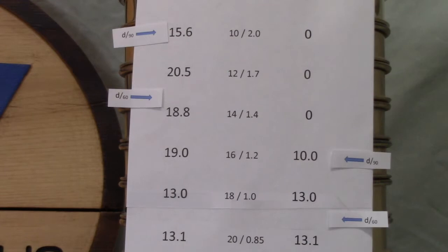Remember that it's the largest fraction of material in a filter that is the hardest to fluidize. Or, another way to say it is, the fluidization velocity required to backwash a granular filter media is determined by the largest particles in that filter bed. Based on the samples in front of us, the material on the left, which has material as large as 2.3 millimeters, would take significantly greater backwash flow velocity than the sample on the right in order to fluidize effectively.